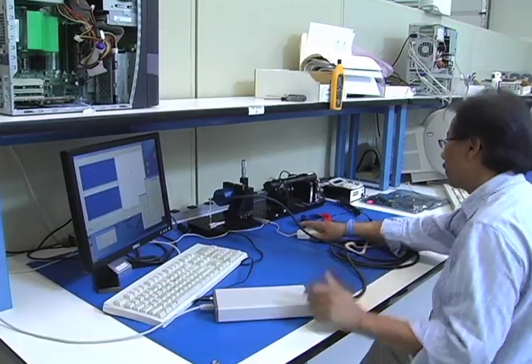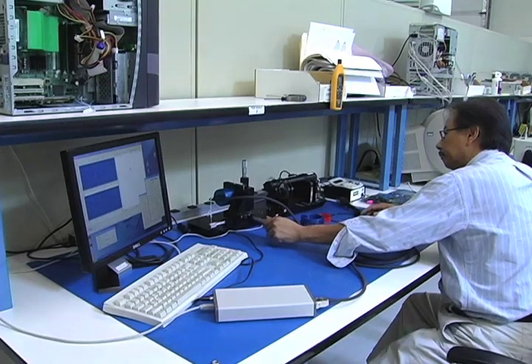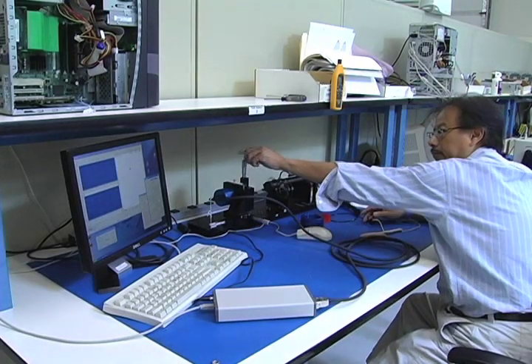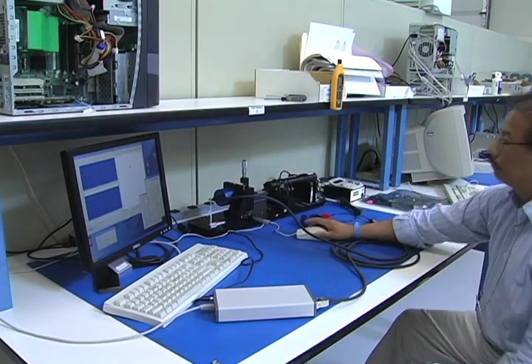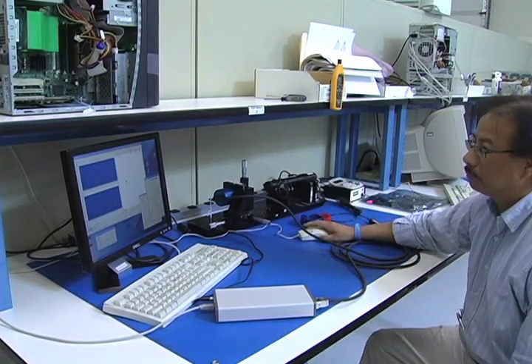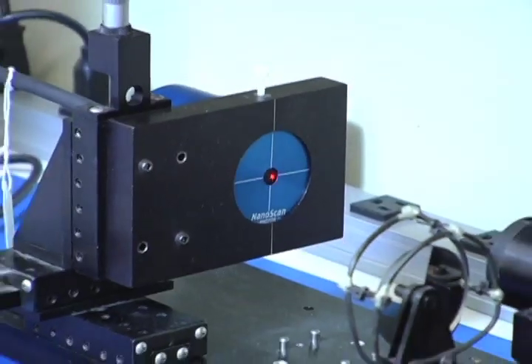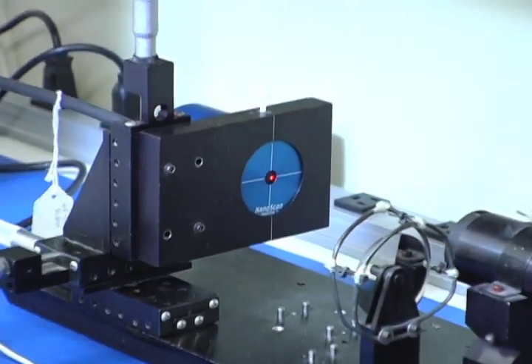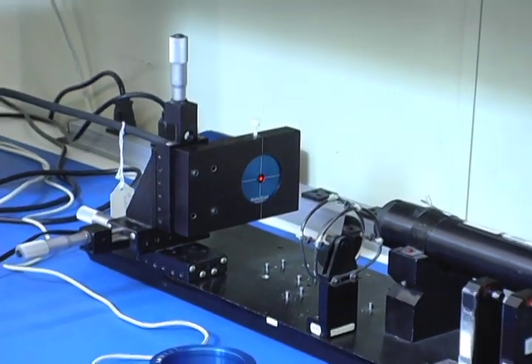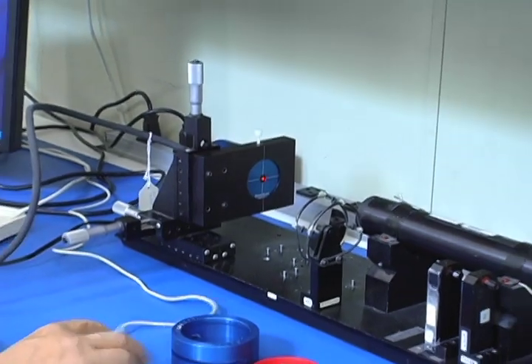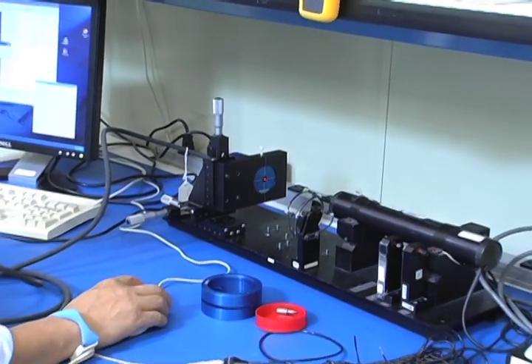Photon scanning slit profilers provide a simple method that works well for both CW and multi-kilohertz and above pulsed beams. The profiler is placed in line with the laser beam and measures focused beams with little or no beam attenuation.